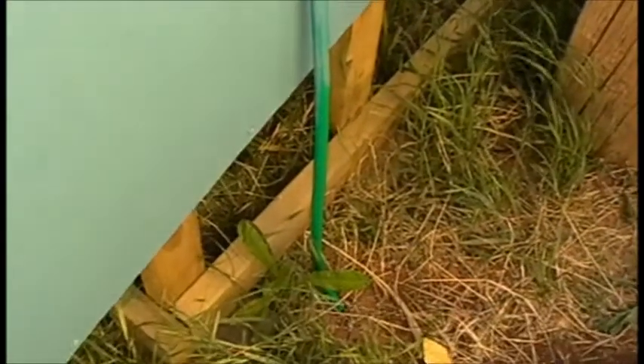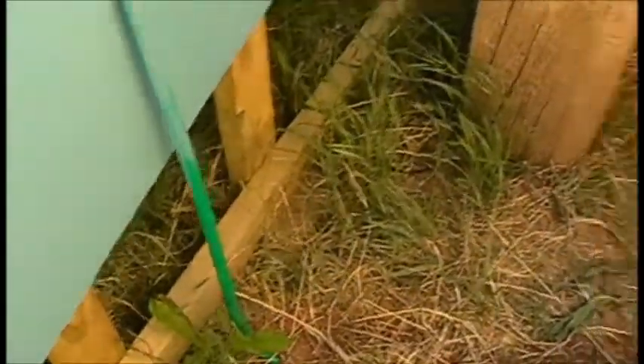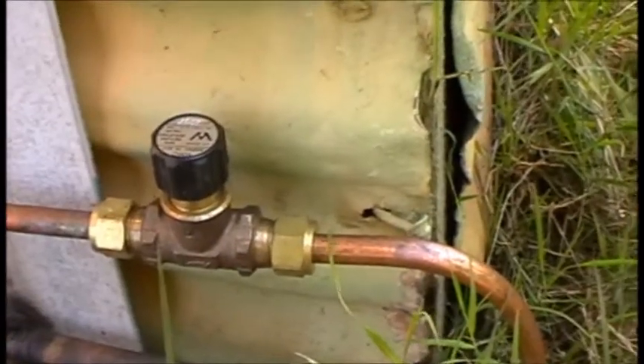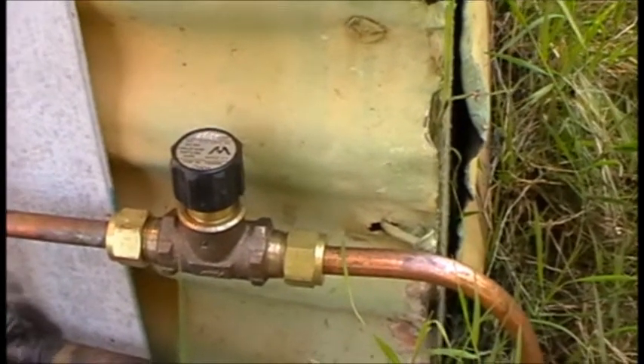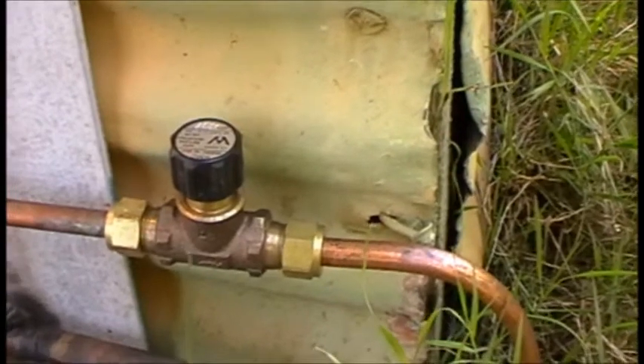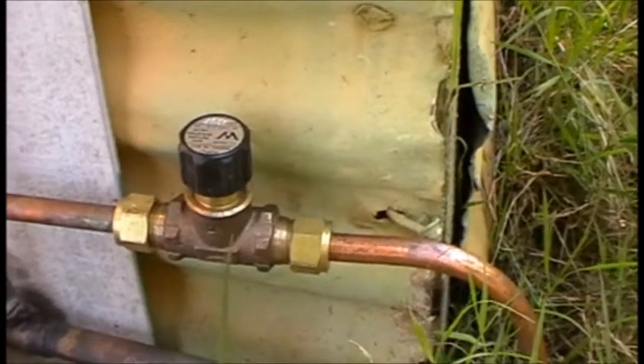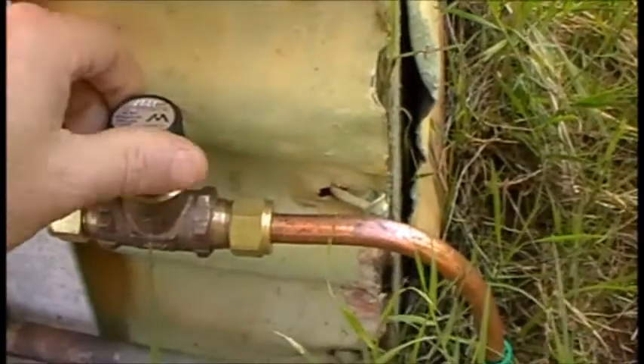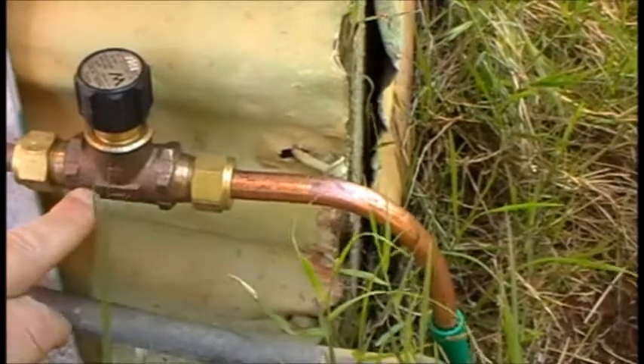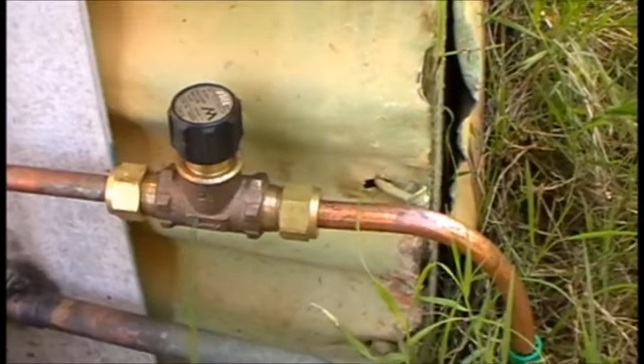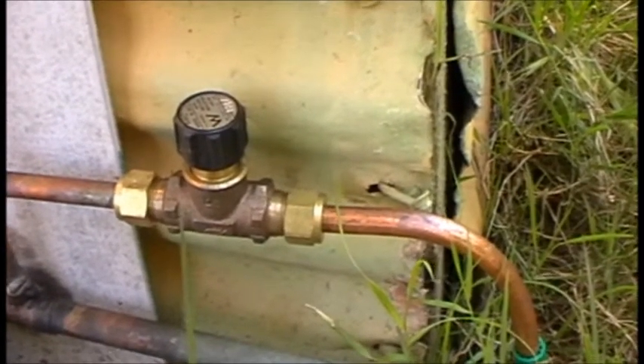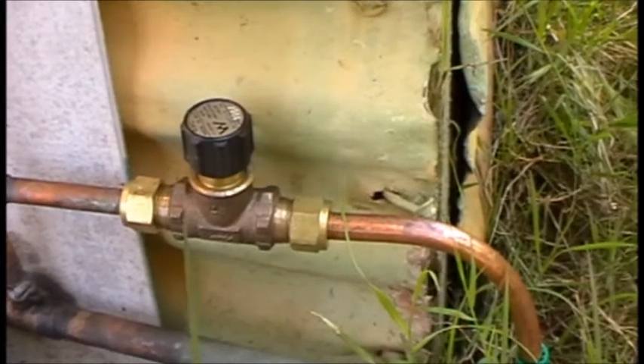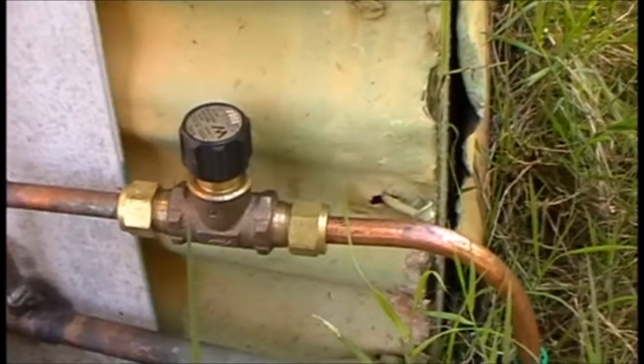Look at the inlet here. Cold water straight off the mains. This is what we call a duo valve. It's very important that any water that's not heated to 60 degrees Celsius is protected from flying backwards into the drinking water supply. Duo valve comprises an isolation valve, and inside there's a check valve so that no water can flow backwards. Because the batch heater doesn't always heat to 60 or higher degrees, there's the potential for bacteria to grow in the water that's contained inside the 250 litre tank.